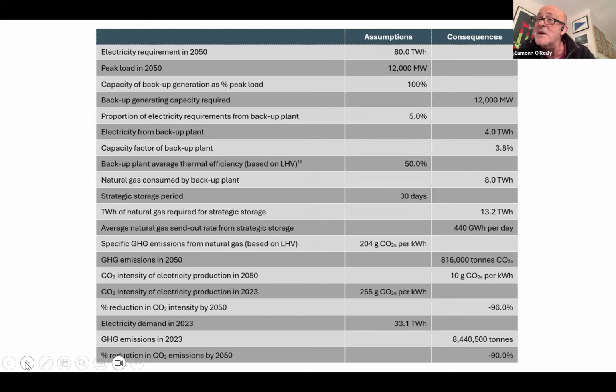4 terawatt hours from 12,000 megawatts of plant means it's hardly ever running, giving a capacity factor of 3.8%. So you have a very, very expensive set of assets sitting there doing very little, which you absolutely can't operate without. We run on through the figures with bits of logic, which I hope are relatively straightforward to follow in the report, and come up with a natural gas storage requirement of 13.2 terawatt hours, LHV, lower heating value of gas, and a send-out rate, a very high peak rate, of 440 gigawatt hours per day. So if you're optimistic we can get a lot of renewables, we can make huge strides reducing greenhouse gas emissions, possibly by 90%, even at a greatly elevated demand of 80 terawatt hours by 2050.